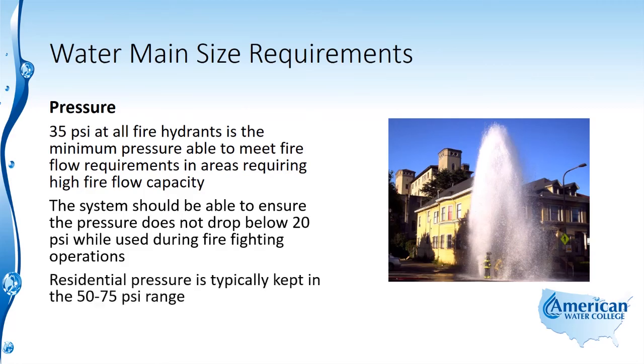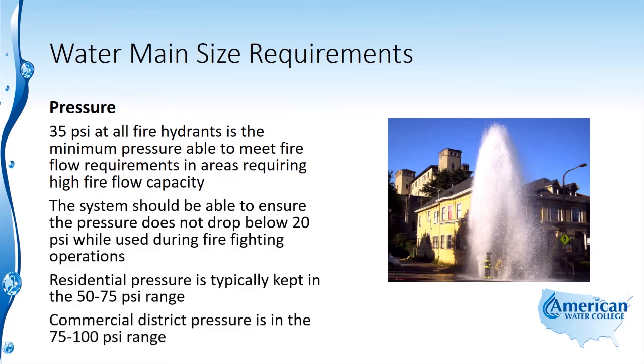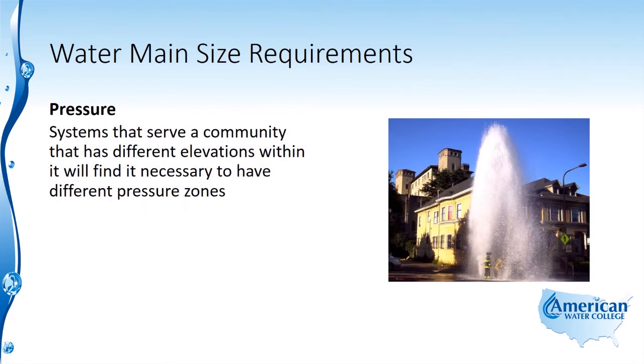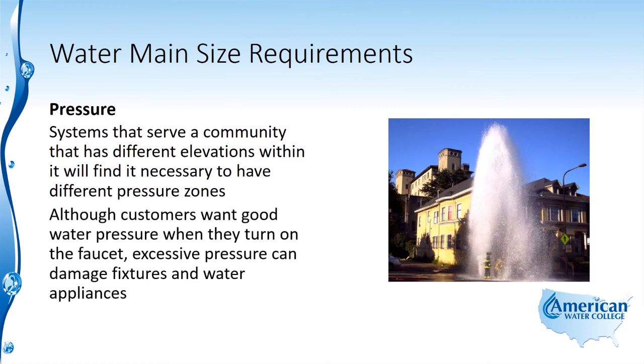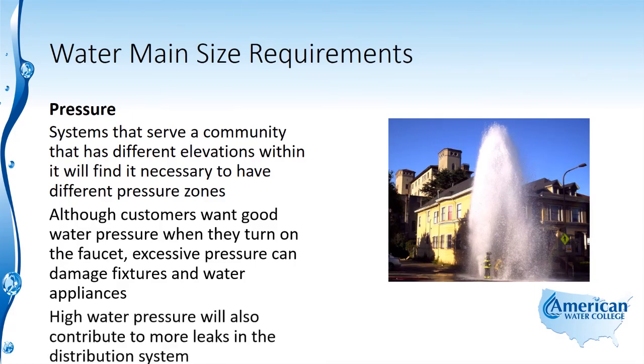Residential pressure is typically kept in the 50 to 75 PSI range, while commercial district pressure is in the 75 to 100 PSI range. Systems that serve a community with different elevations will find it necessary to have different pressure zones. Although customers want good water pressure, excessive pressure can damage fixtures and water appliances, and will also contribute to more leaks in the distribution system.